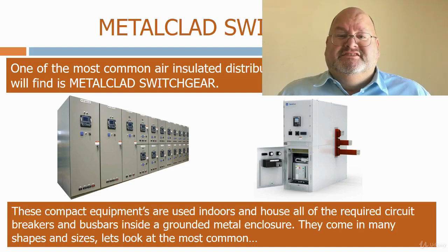Metal-clad switchgear is considered to be maintenance-free and very reliable. The instances of electrical breakdown are very low. The main cause of failure in my career is having rodents or insects getting inside the bus bar or circuit breaker chambers, shorting out the bus bars, and one instance of a bus bar support insulator failing due to a crack during manufacturing.